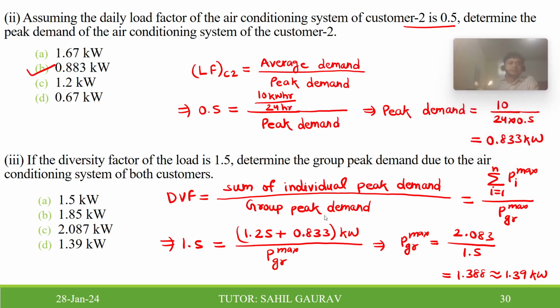The sum of individual peak demand we have found in the previous two subparts. So 1.25 plus 0.833 kilowatt. From there you can find the group peak demand of both the customers. That will come as 1.39 kilowatt.